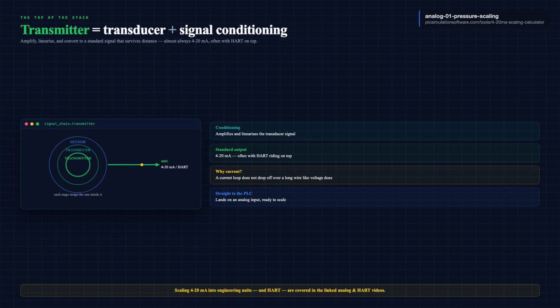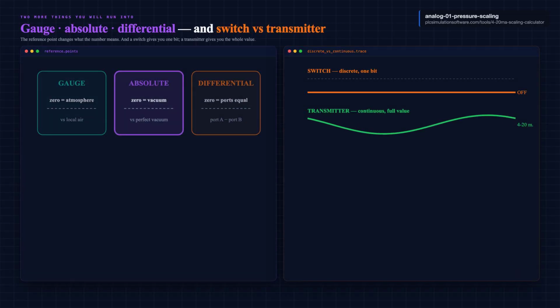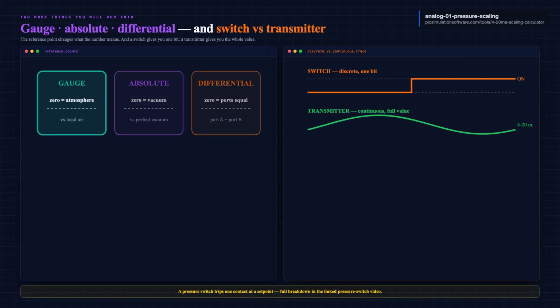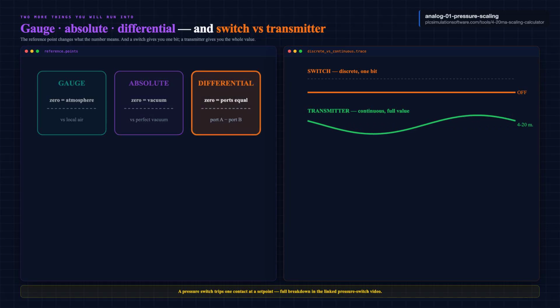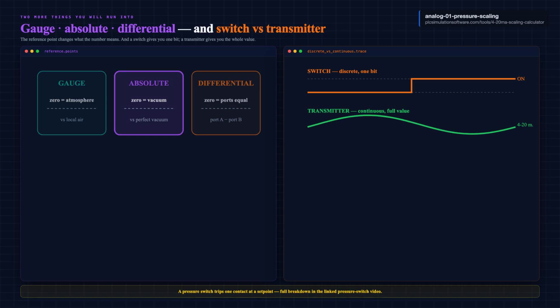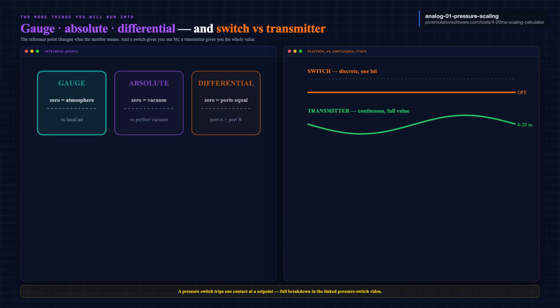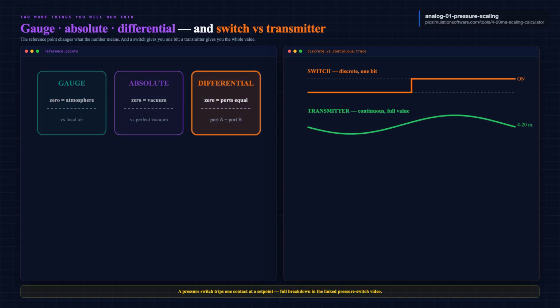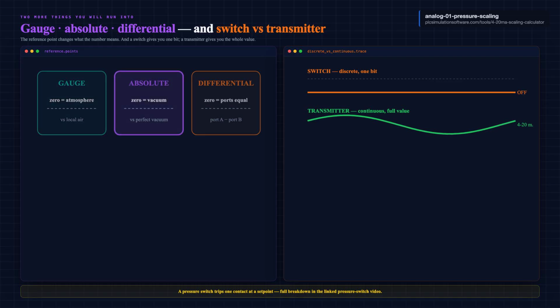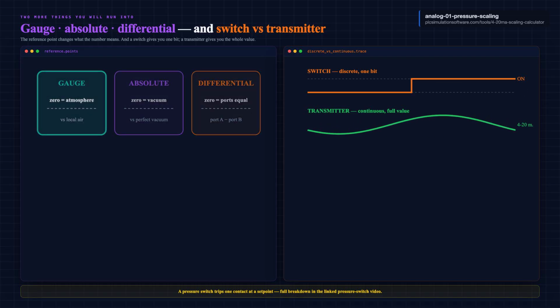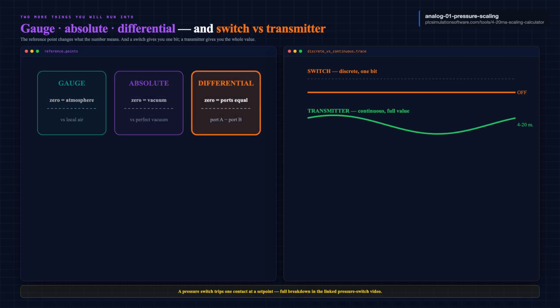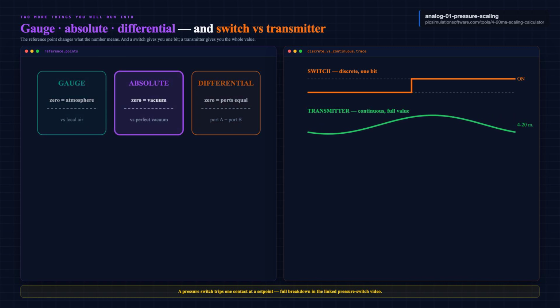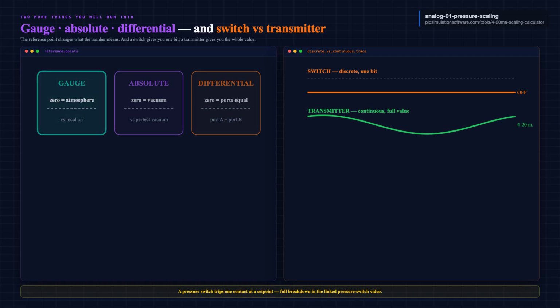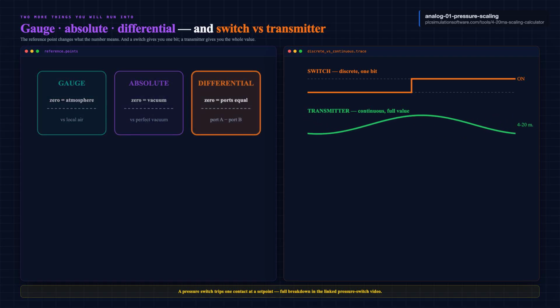Two more things you will run into. First, the reference. Pressure is always measured against something. Gauge pressure is measured against the local atmosphere. 0 means atmospheric. Absolute pressure is measured against a vacuum. 0 means a true vacuum. And differential pressure is the difference between two ports, which is how you measure flow and level. Same device family, 3 different reference points, 3 different meanings for the number.